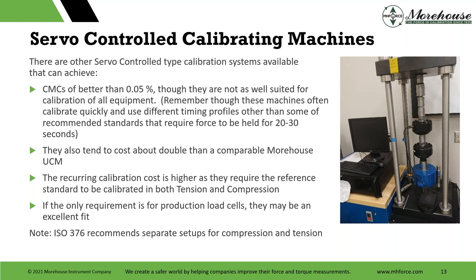They tend to cost about double a comparable Morehouse UCM. That's without the automation. The recurring calibration cost is higher, as they require the reference to be calibrated in both tension and compression. And if the only requirement is production load cells, what you're calibrating often determines what reference equipment makes the most sense. And if you're doing production load cells, where you're just doing 5-point calibrations, these might be an excellent fit. We've had people ask us specifically about a UCM for those occasions, in which we've said this is a better fit. It's just evaluating all the factors.